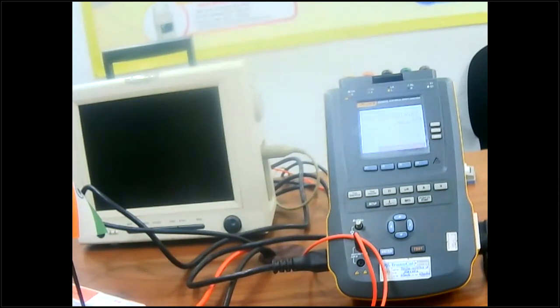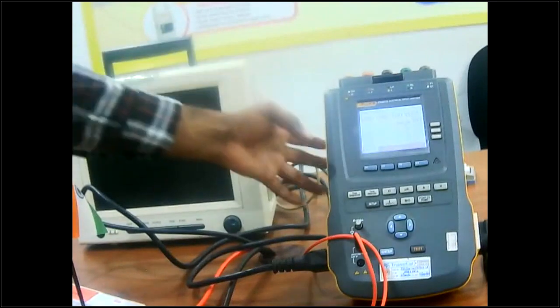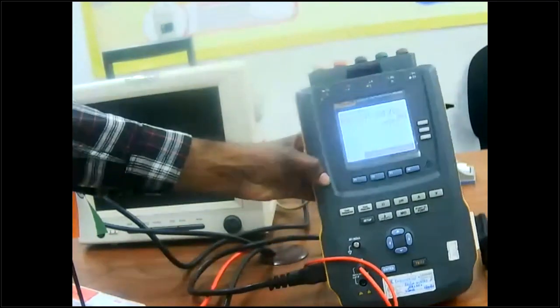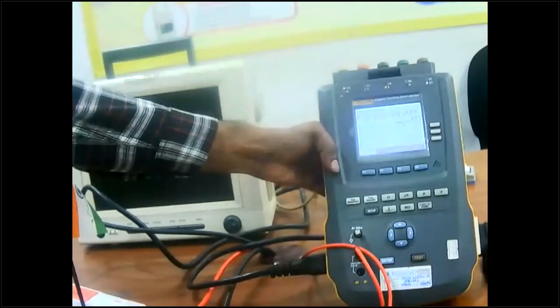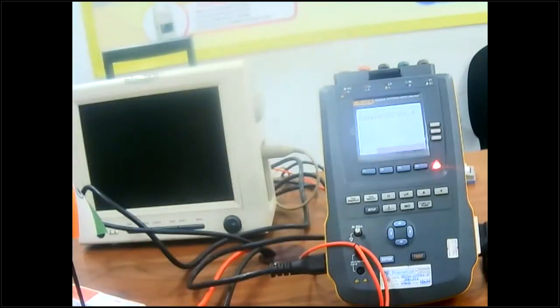Now we are going to do mains to protective earth. You are able to see, I believe. Then press test. Please understand that OL is not for the resistance. If it is showing OL, it's acceptable because it is more than the required resistance.